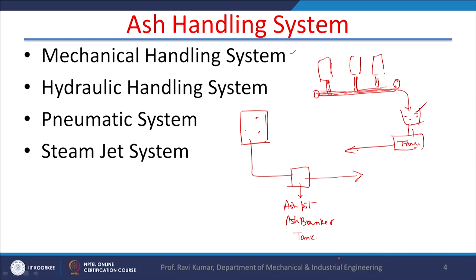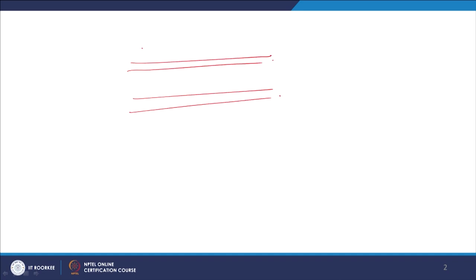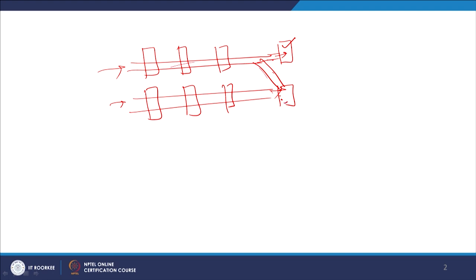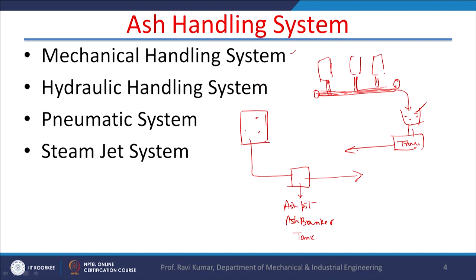There is a hydraulic handling system also. In the hydraulic system, there is a water trough and you can have a number of water troughs. Coal ash comes from the source, water comes from one side with forced circulation, and there are sumps where water and ash are dumped. Sometimes more than two or three sumps are used so that when one sump is filled, flow is diverted to another sump while the first sump is being cleared. This is the hydraulic system used for handling ash in thermal power plants.